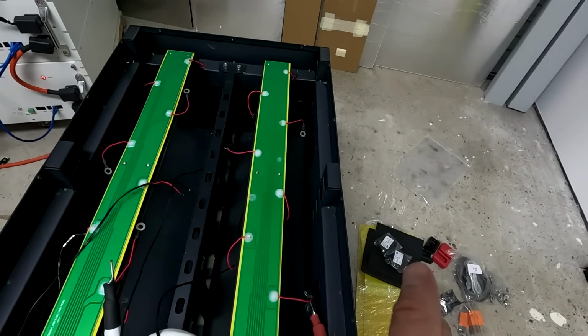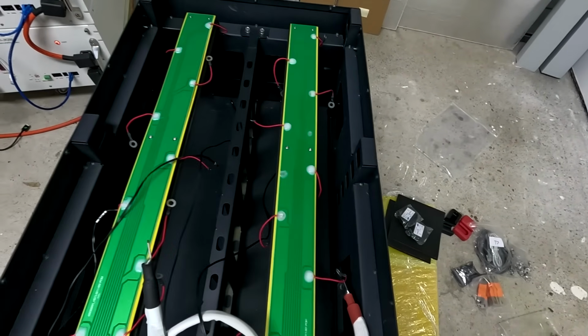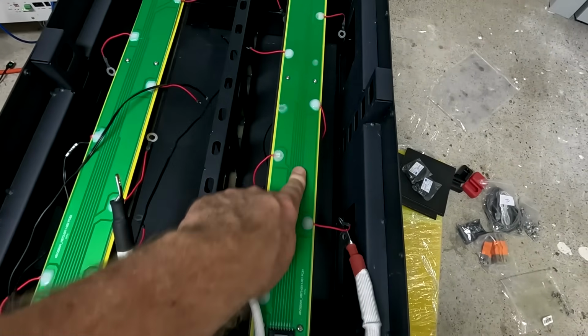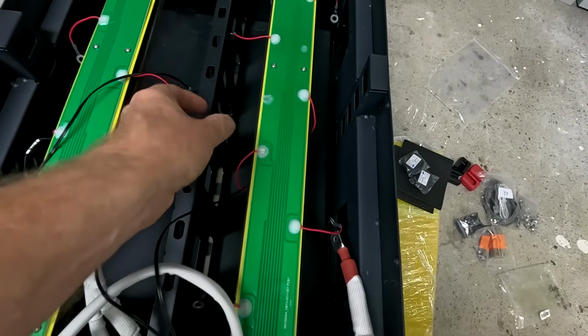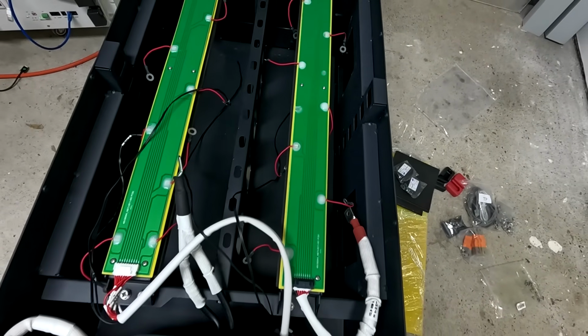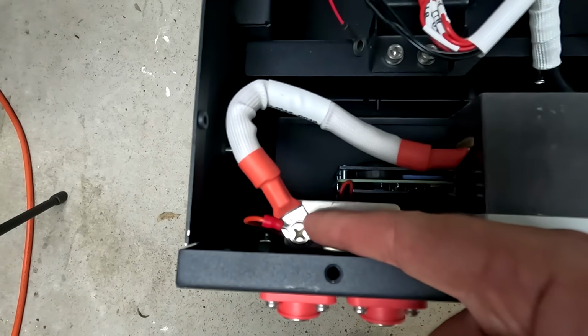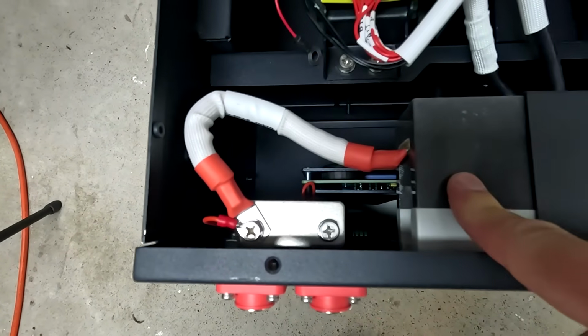Either have these epoxy sheets with a channel so you can slot them in, or have them combined on the PCB with short cables and ring lugs to connect to the terminals. The positive of the BMS definitely does not belong on the output of the circuit breaker.